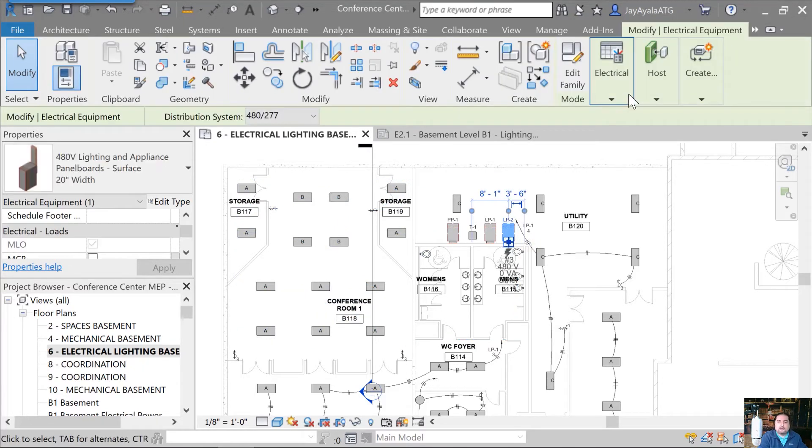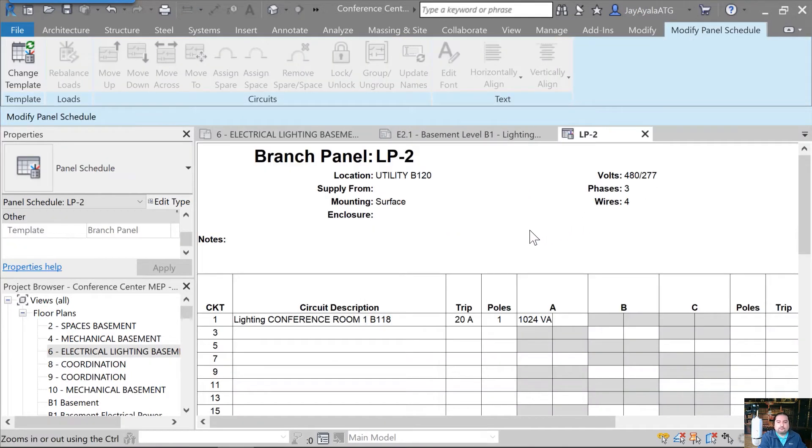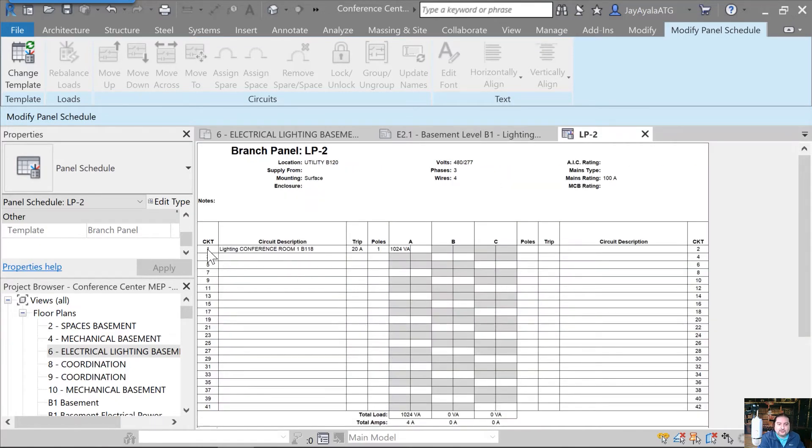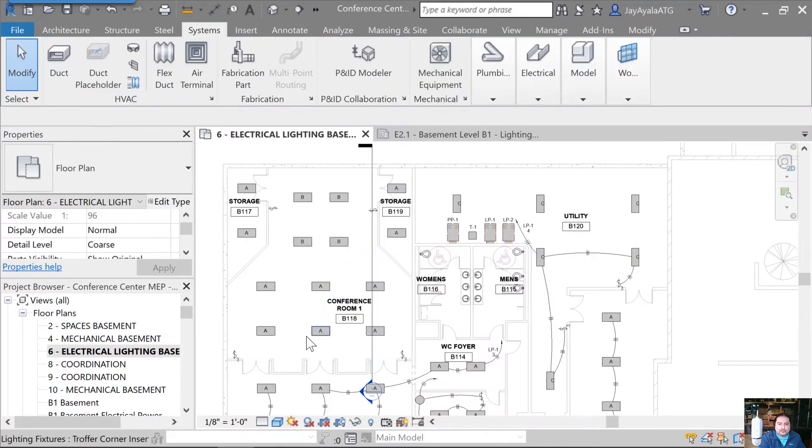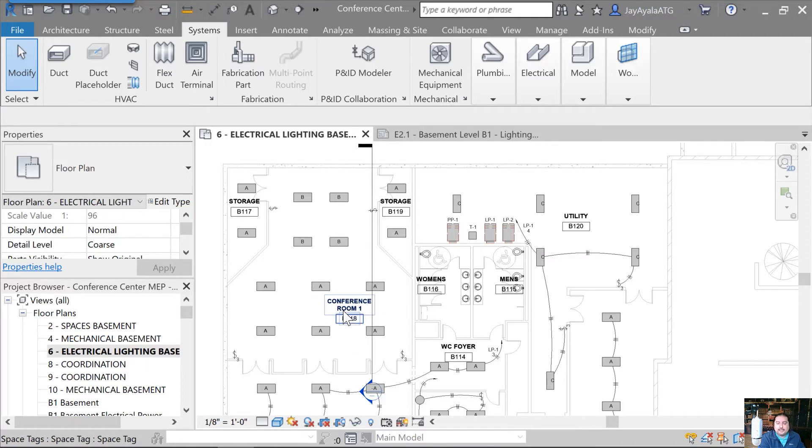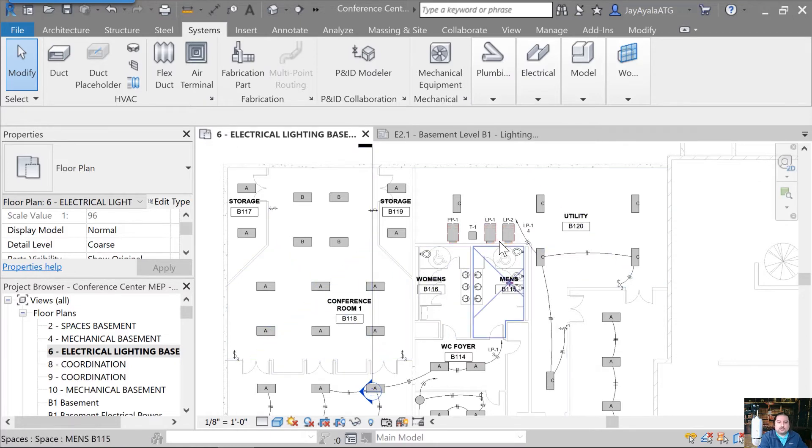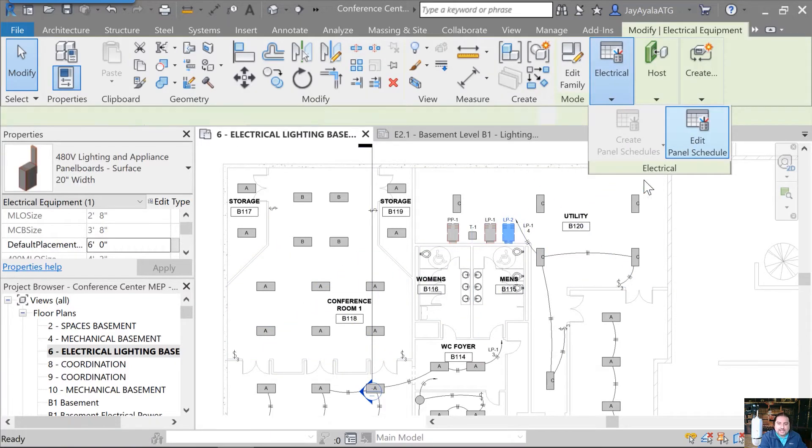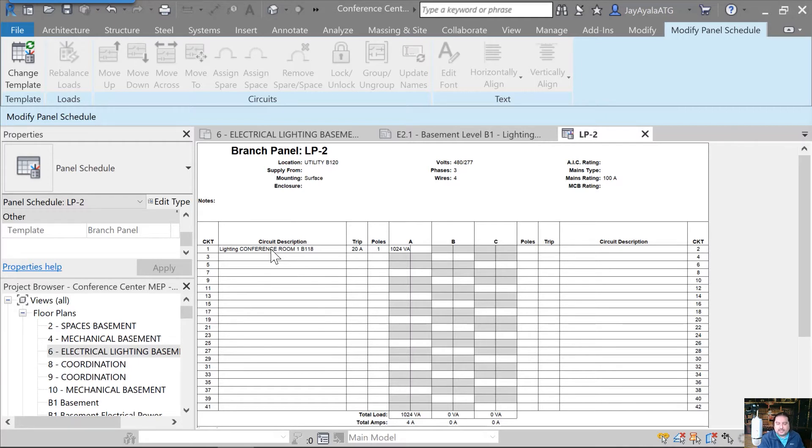If I simply hover my mouse over that lighting fixture and hit the tab button on my keyboard, I can easily see the relation of all of the items and where you can even see where the routing would be for wiring and it's pointing towards that panel LP-2. So if I go look at panel LP-2 now, here's the electrical panel schedule information. I'll just choose the default template and you can see that it already filled itself in circuit number one lighting conference room one B118. So where did that information come from? Well, that came from when I selected that first item, it happened to be in conference room one B118 and the category happens to be lighting. So when we look at that particular panel schedule here, it's picking up the information from the room for free. And the thing about this is the architects are already doing that. They're already typing in the names of the rooms and the numbers of the rooms. You're getting that information for free if you're using Revit. So let's leverage that information.